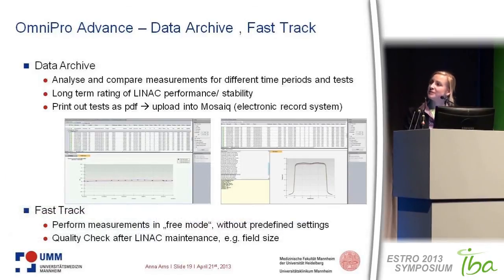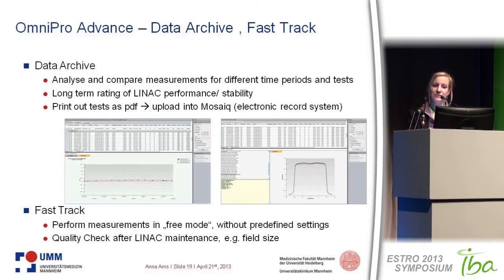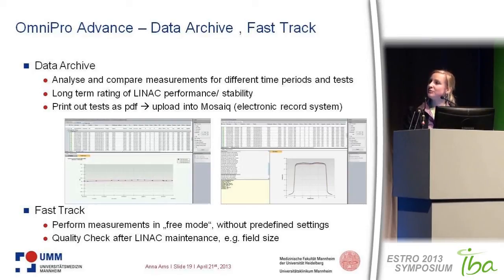The last section is Fast Track, where you can perform measurements in free mode. You don't have to pre-define any settings; you just put the device on the couch and measure directly. This helps a lot with Linac maintenance — for example, if you had an error in field size you can directly modify and verify.